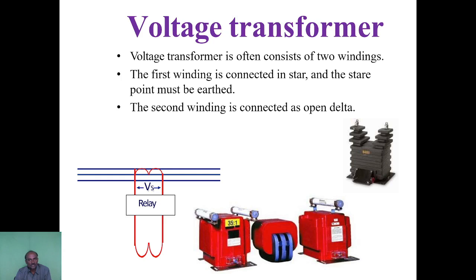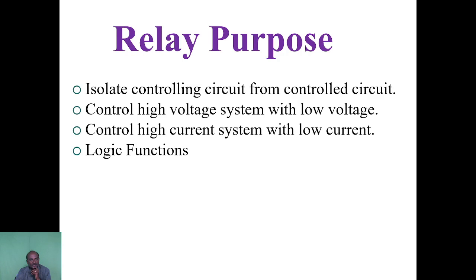Then the voltage transformer. It is also for measurement, and a voltage transformer often consists of 2 windings. The first winding is connected in star. The second winding is connected as open delta.